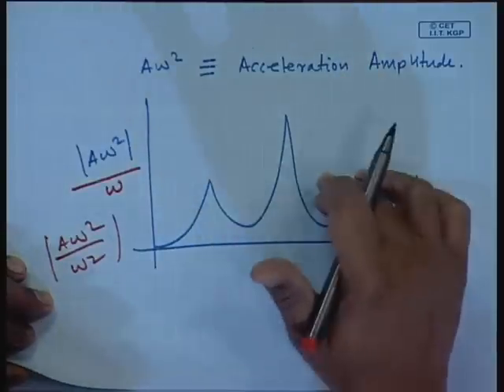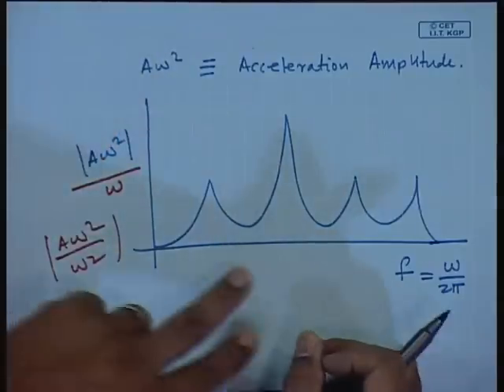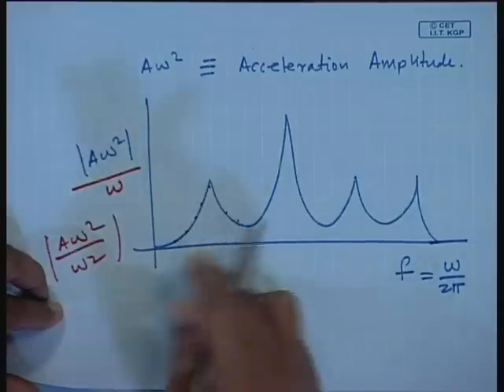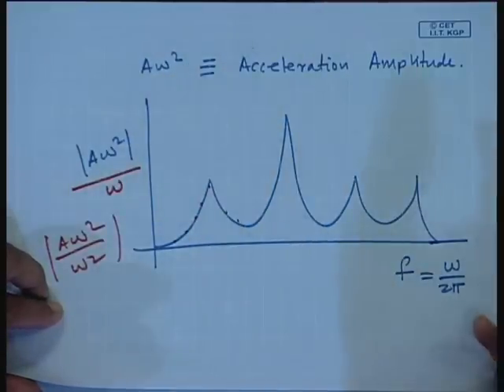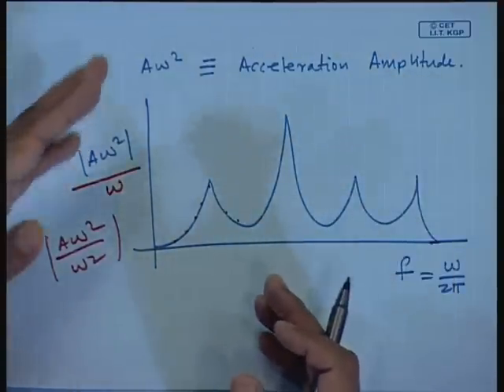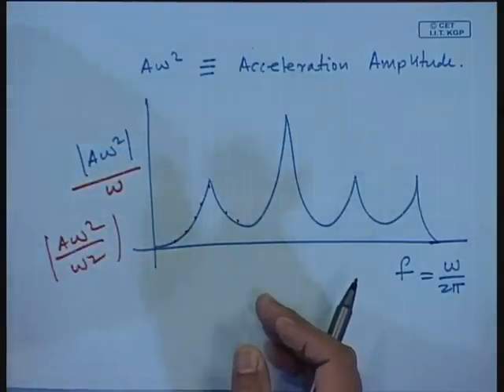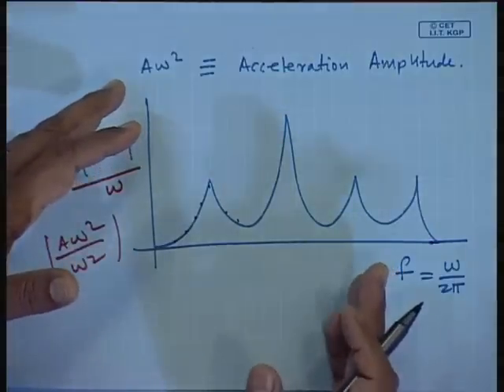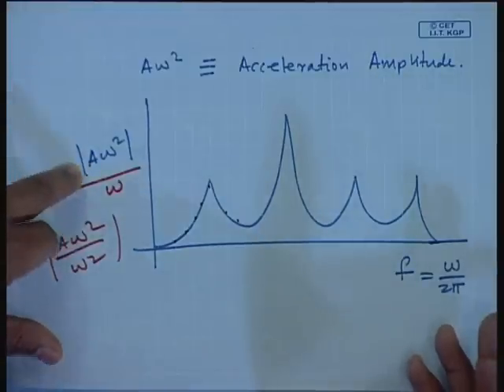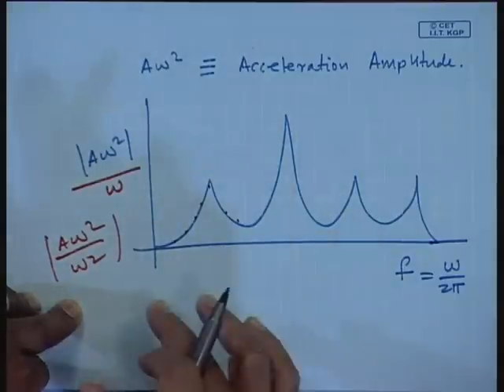This is done as post-processing. Many vibration meters do it electronically - once you measure with an accelerometer you measure the acceleration Aω². Once you do the Fourier analysis you get the spectrum, and at every frequency you divide by ω or ω² to get the velocity or displacement spectrum.